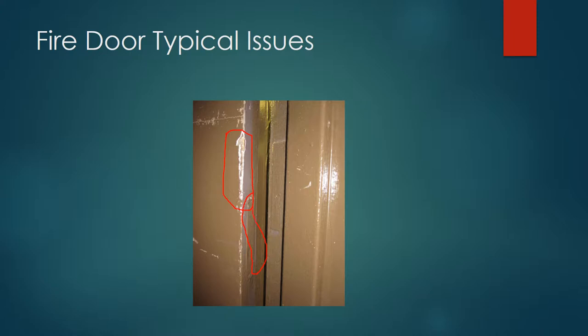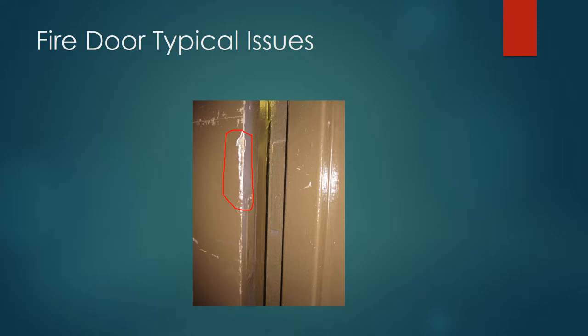But the real issue is over here — there's a plate that is supposed to identify the rating of the door. You can see by the coloring of the door that the plate has been painted over in the same color, so you're not going to be able to see the rating on that plate. Here you can see the door frame rating and the door rating — both painted over — which is a violation you see pretty commonly in healthcare and other facilities.